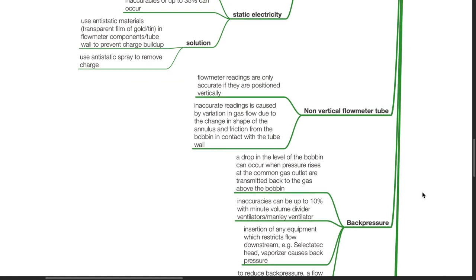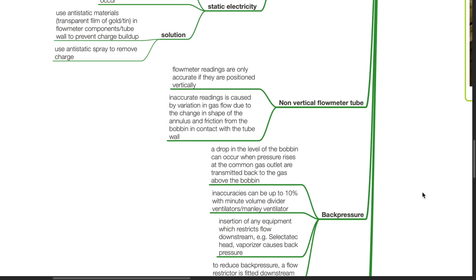Non-vertical flow meter tube: Flow meter readings are only accurate if they are positioned vertically. Inaccurate readings are caused by variation in gas flow due to the change in shape of the annulus and friction from the bobbin in contact with the tube wall.